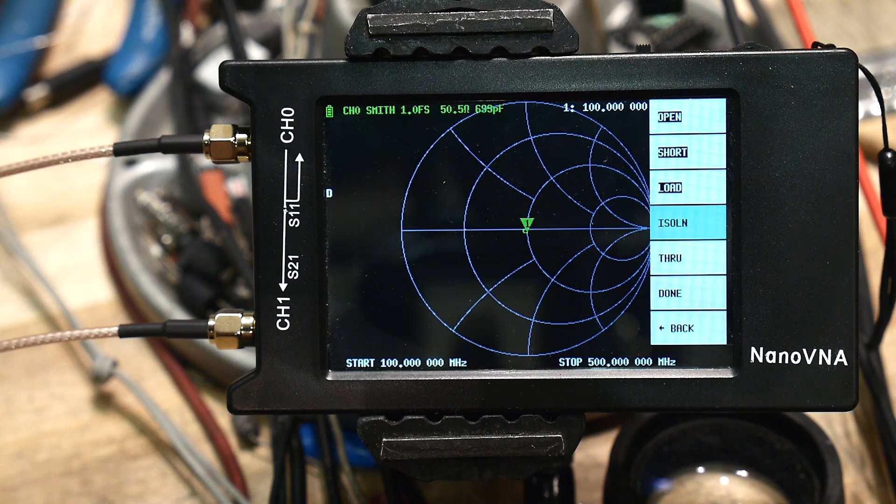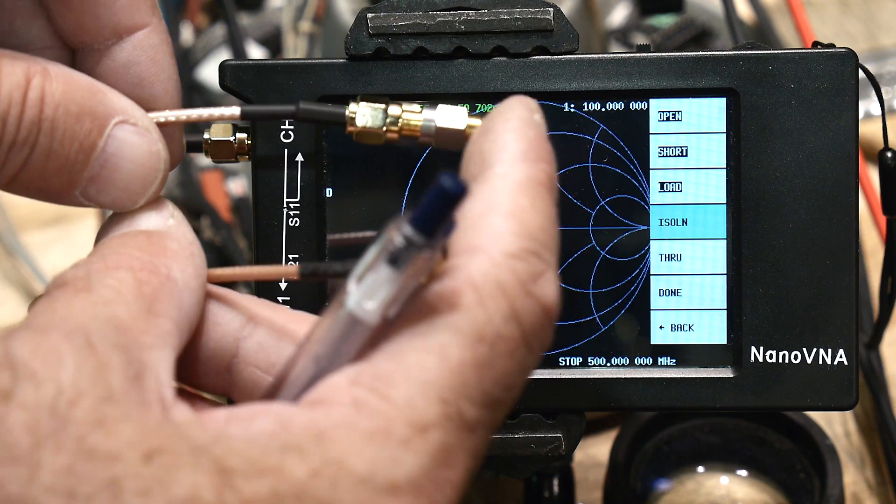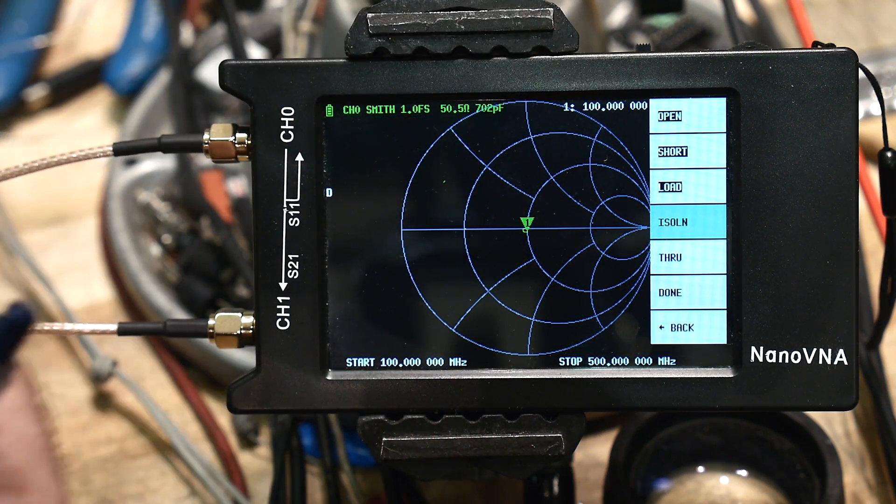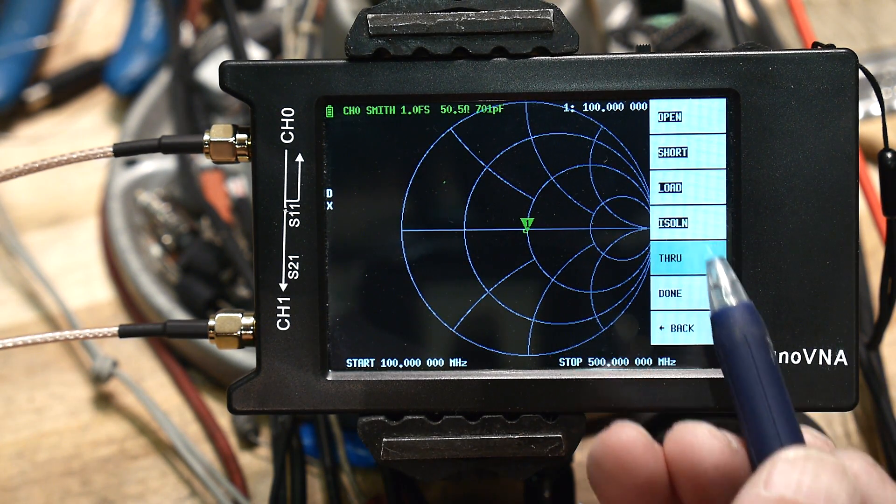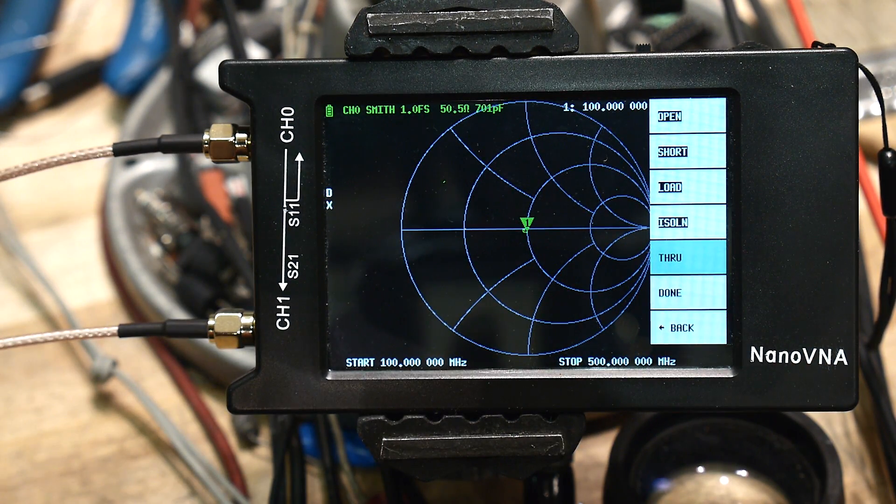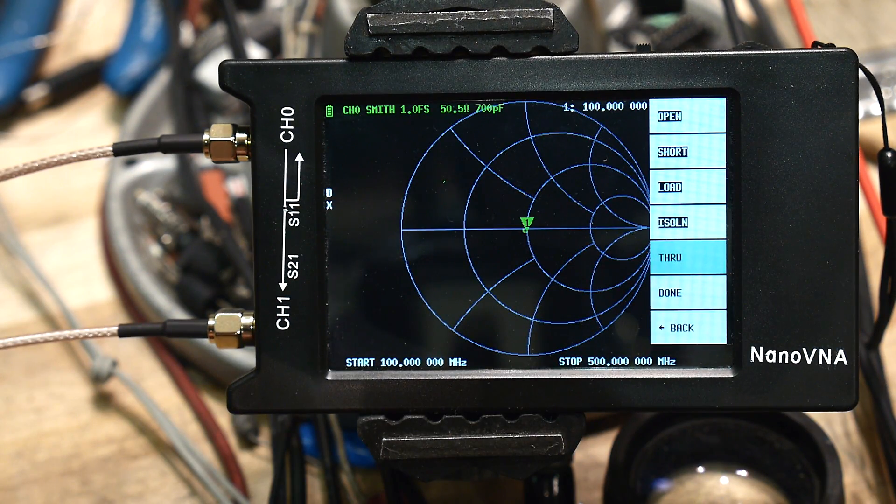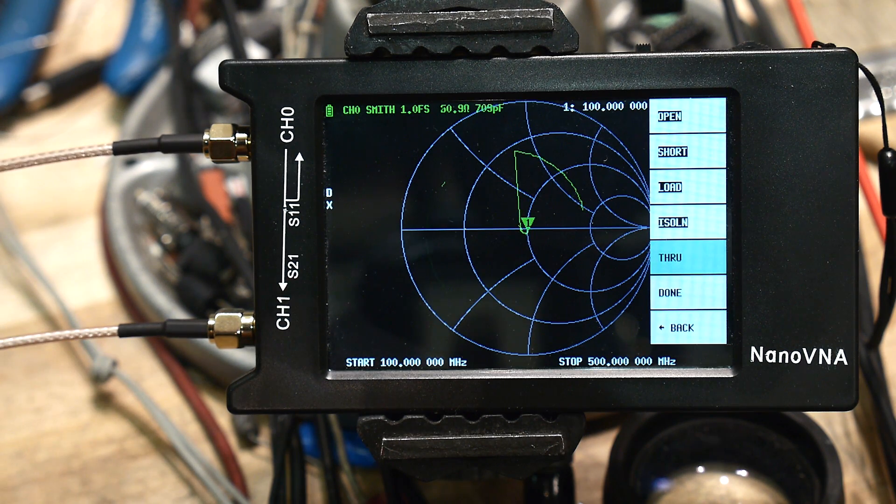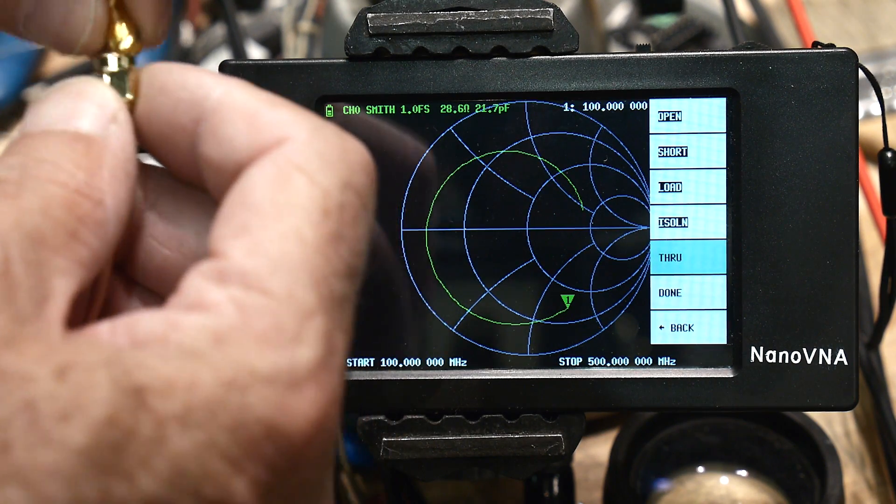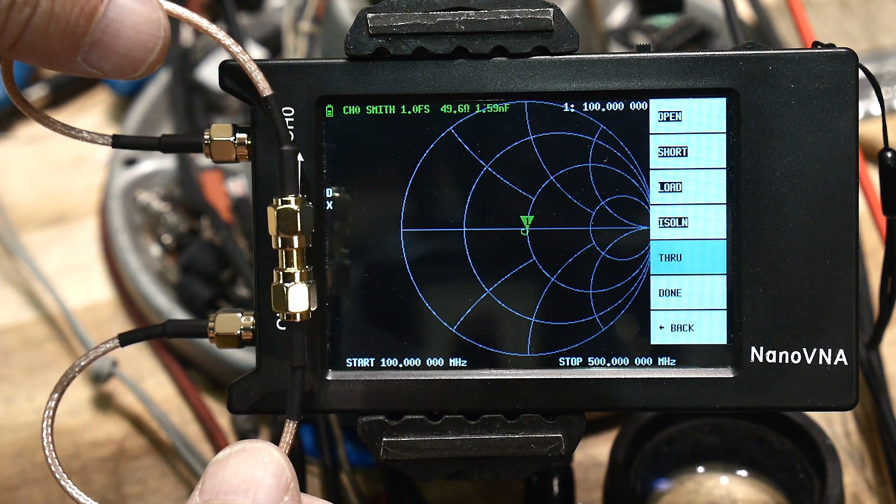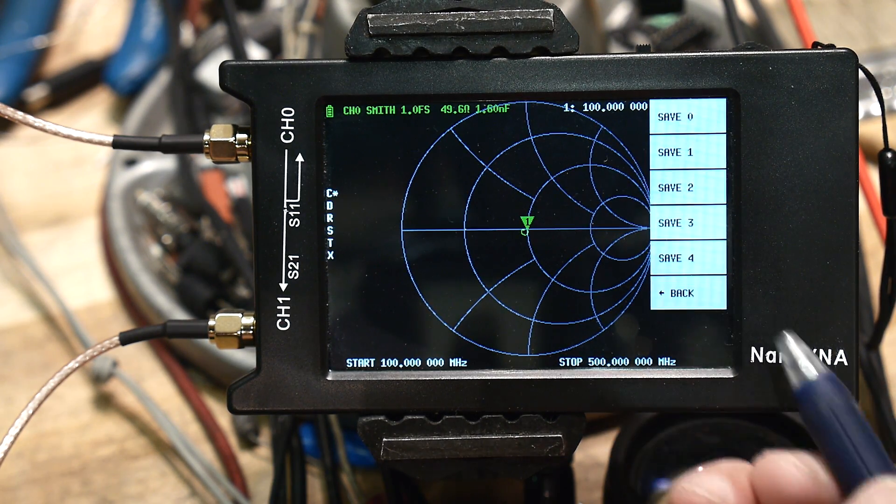And we'll do the load. Okay, now isolation. We haven't touched anything, we still have the load on there and we have this one open. It'd be nice if we had a 50 ohm load to put in here, but that's not supplied. We're going to hit isolation. And that just zeroes out any crosstalk that's in the instrument. And then we're going to do a through. That's going to tell channel 1 how to calibrate itself. So we're going to take that little through connector and put it between the two cables. We have channel 1 and channel 0 shorted together with this little connector. And we're going to do through, and then done. And let's do a save 0. And now it's all ready to go.